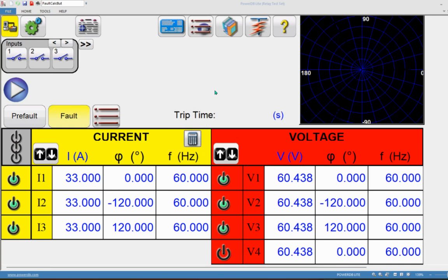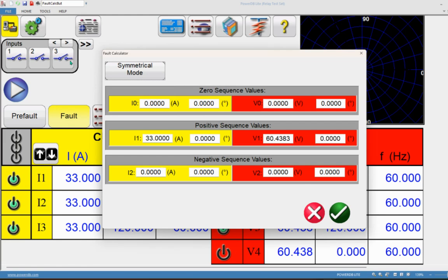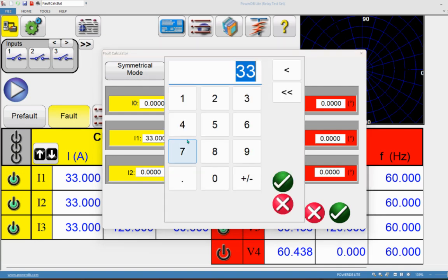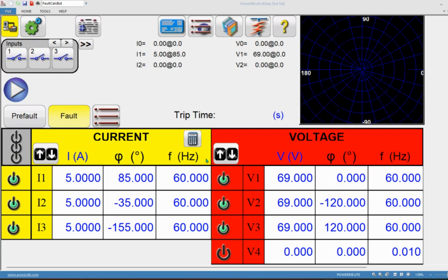To open the symmetrical mode, go to the fault calculator in the home screen. Click on the fault calculator, then click the drop-down options and select symmetrical mode. Symmetrical mode has three options: positive sequence voltage and current setting, negative sequence voltage and current setting, and zero sequence voltage and current setting. For example, set positive sequence current to 5 amps at 85 degrees, and positive sequence voltage to 69 volts at zero degrees, then click OK.